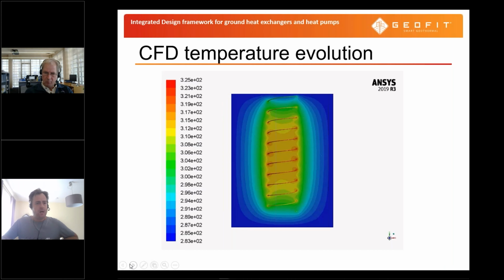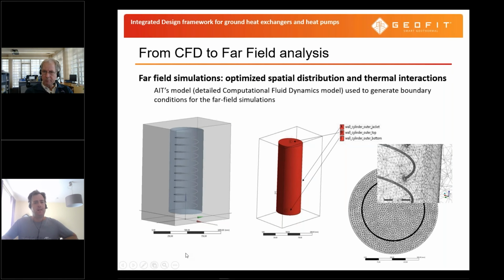Out of those near field analyses, it is also crucial to take a look at arrays of such spiral-shaped collectors or earth baskets. The colleagues from EureCut, in the person of Manuel, did far field simulations where they took our result from the near field simulations as the boundary conditions for their far field analysis. In that way, it's not needed to mesh and mimic this detailed geometry of the spiral shape. They solely used this surface and put our boundary conditions in as their input for those far field analyses.